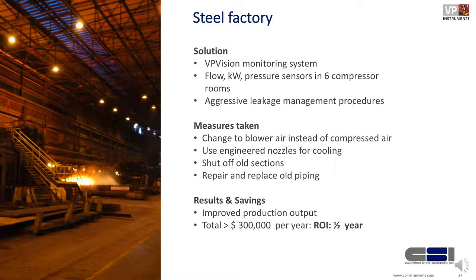There was air being used from the compressed air system where, actually, blower air could be used. They used their homemade engineered nozzles for cooling, and we changed those for engineered nozzles. We were able to detect sections that no longer required air, but air was still being fed into those sections, and there were hoses, nipples, and all kinds of things leaking. So it was pretty easy just to shut those sections off.